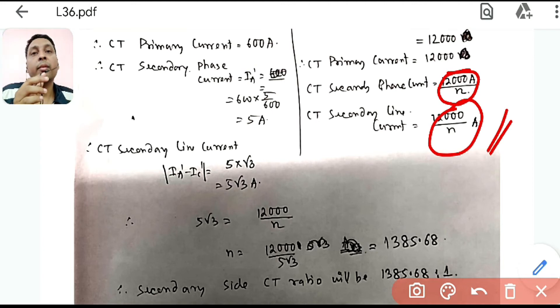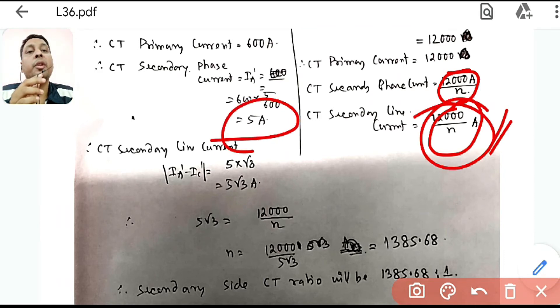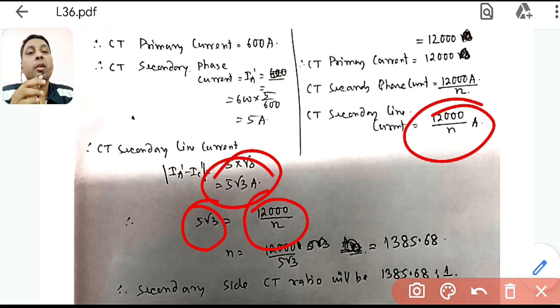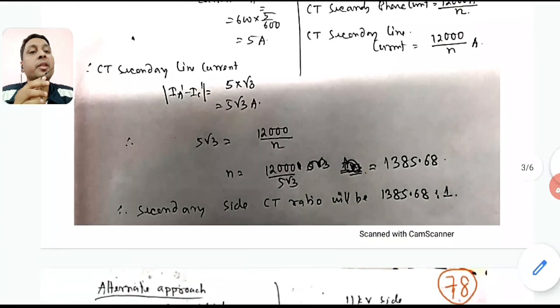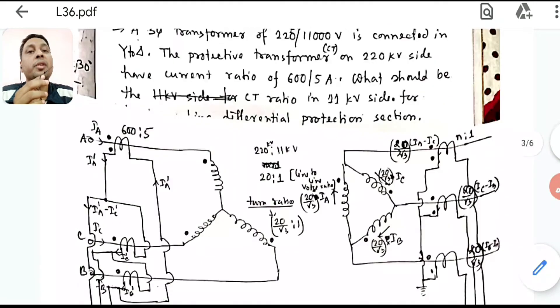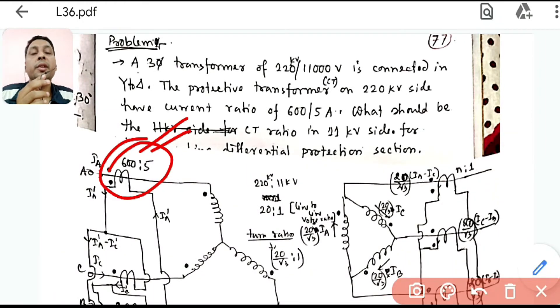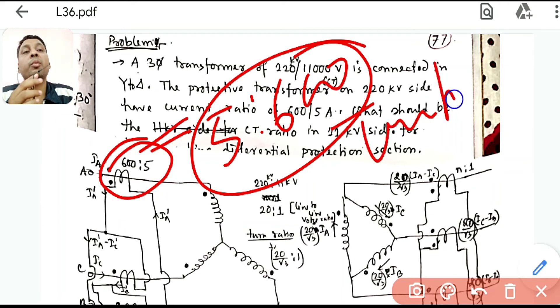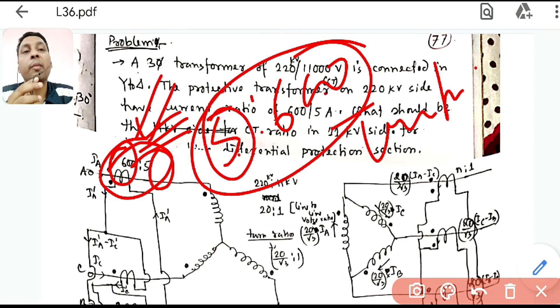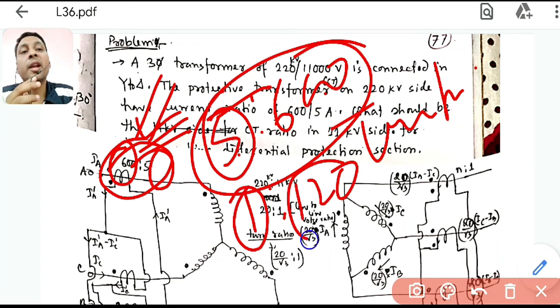For normal operation in a differential scheme, the currents on both sides entering the relay must be equal. Setting 12,000/n equal to 5√3 gives the required CT ratio n. Note that a CT ratio of 600:5 means a current ratio — if 600 A flows in the primary then 5 A flows in the secondary — and the actual turns ratio is the inverse: 5:600, or 1:120.